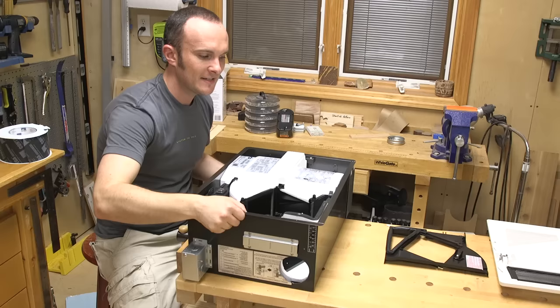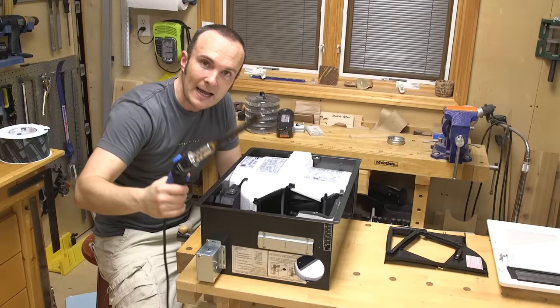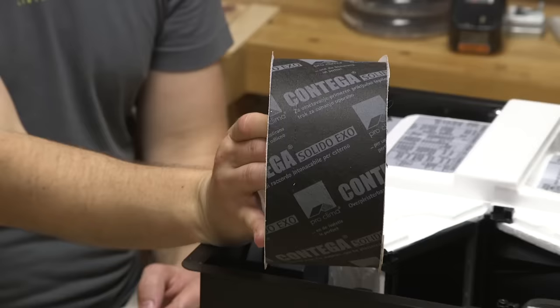It's very important to replace like for like — if you drill a smaller hole it introduces back pressure that won't let the unit run properly. After drilling the hole in the metal, we also had to cut a hole in the styrofoam inside, because there's very well-formed styrofoam with curved edges managing airflow. We drilled the metal, then cut the styrofoam with a hot knife insulation tool — I love this thing, it's come in very handy throughout this whole process.